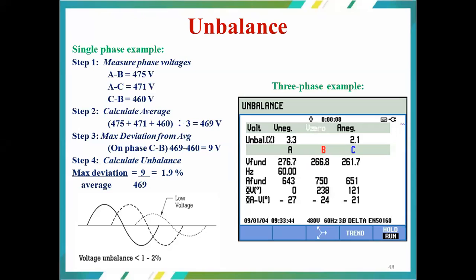And the next one is the unbalance. In the case of level 1 charging stations, we discussed 120, and in level 2 charging stations, we discussed 240. In both cases, we rely on the single phase AC supply system. If all the charging stations of a particular locality or facility are connected to the A phase, the B phase or the C phase, then that particular phase voltage is going to get reduced, which is a problem when it comes to the 3-phase system or a transformer.